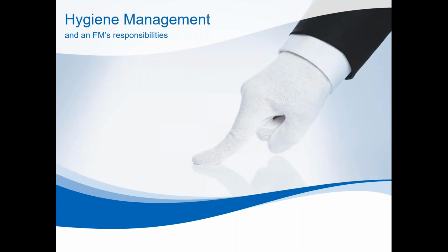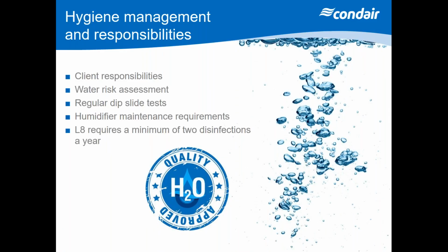So talking of disinfections, talking about hygiene management. Now, these humidifiers tend to fall into the category of HSG 274 Part 3. So I'm assuming some of you guys have got cooling towers in your building. These humidifiers should be added to your water management scheme to make sure that they're being tested on a regular basis. And normally what we recommend to clients is that they should be doing a self-risk assessment of their water supplies or the application to understand how often they should be checking the conditions of their water. So regular dip slides being put in place.